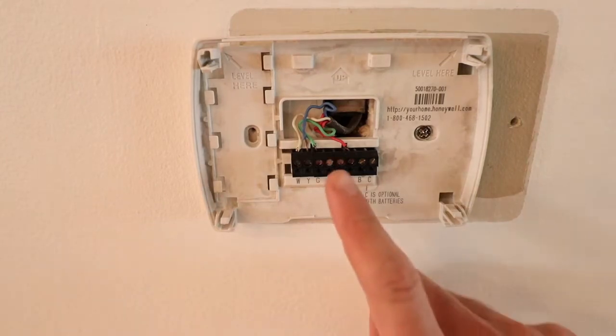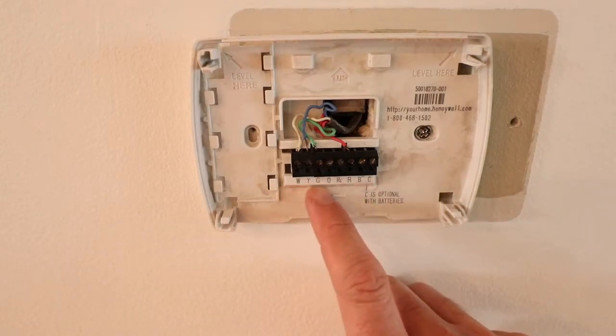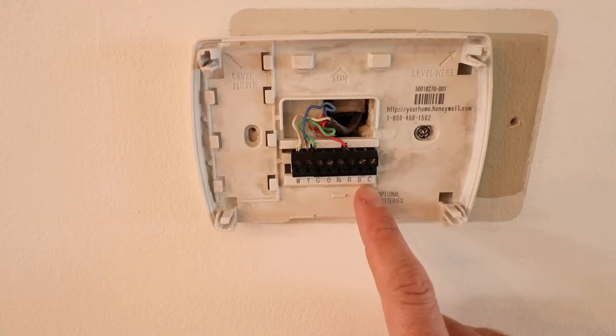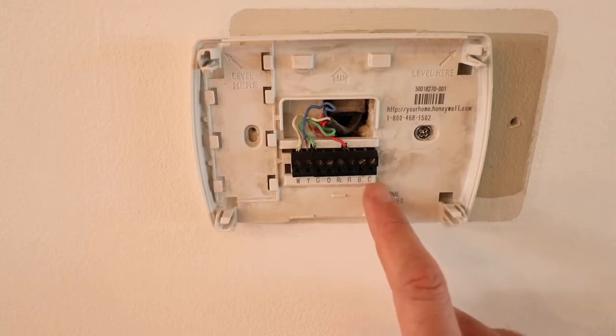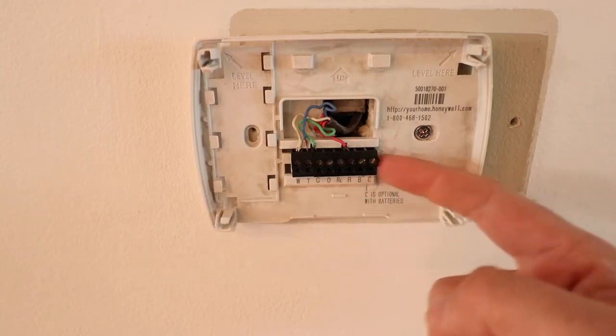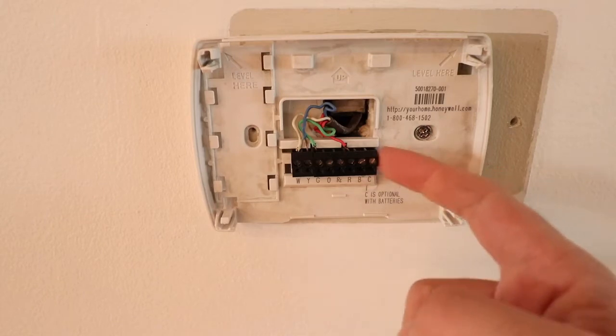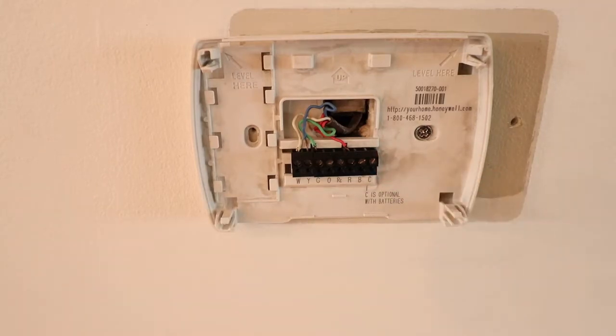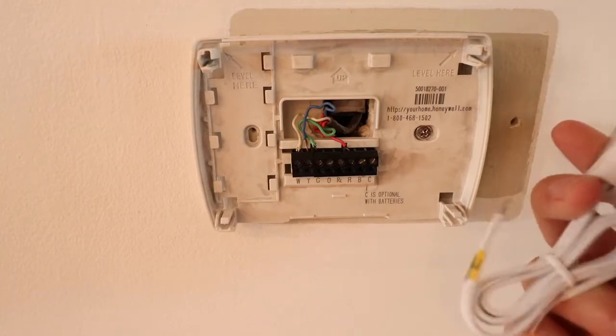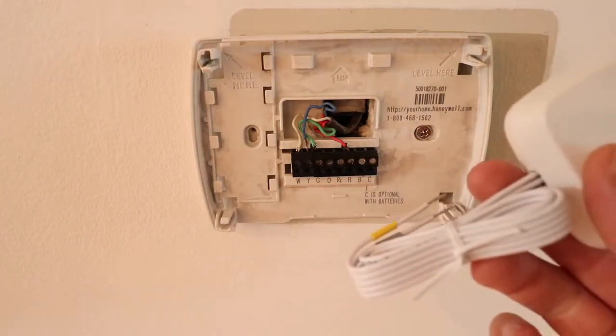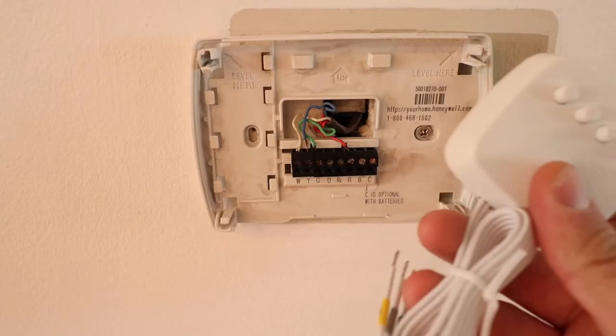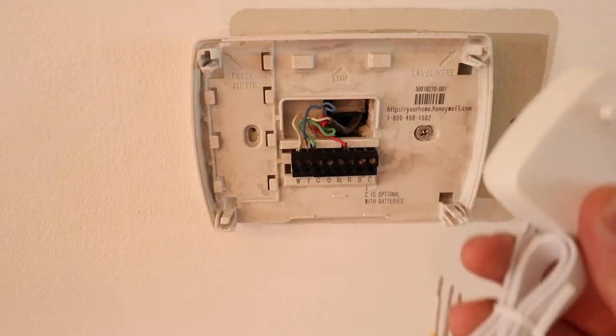You can see down here we have different letters for each of the wires, and what we're looking for is the C wire. We can see we don't have a C wire, also known as a common wire, which means we're going to need the common wire adapter that comes with the Ecobee thermostat, and we'll need to install this inside our HVAC system at the control board.